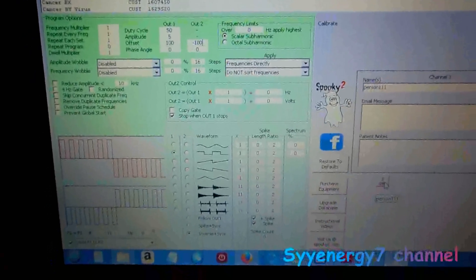Start it up. Now this is interesting — it's going up five volts, down to zero, up five volts, but it's not going up to ten volts and down to zero. It's going from ten volts to five, then ten to five — it's all positive offset but it's going ten to five, ten to five. It never goes all the way down to zero. I would think you'd want it to go from ten to zero, ten to zero, but it's going ten to five, ten to five, never going into negative.